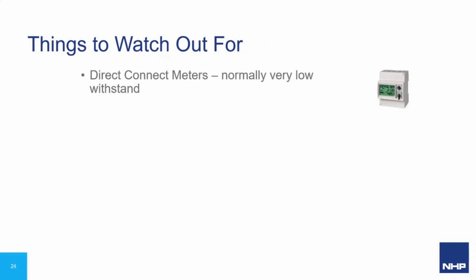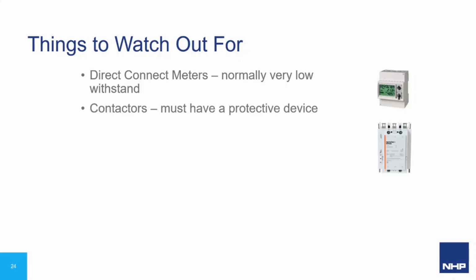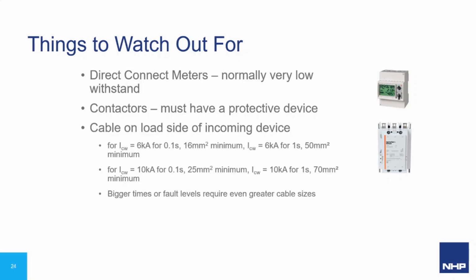Some things we need to watch out for: direct connect meters in high level switchboards, as they normally have a very low withstand. Contactors also, standalone, have a very low withstand. They need a protective device either upstream or in the assembly to protect them.